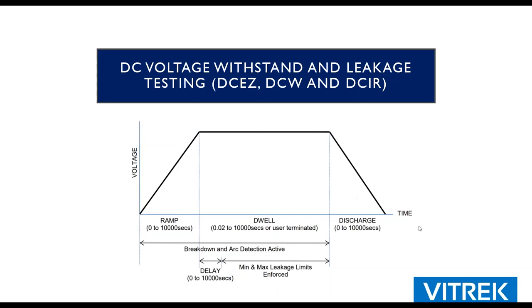We can apply different limits at different parts of the test. And importantly here, we can also have a delay. As you turn the corner from ramping to dwell, especially in DC, you could have very high charge currents right here. Then when we stop charging, you could actually have current reverse slightly or go to zero. And then what you really want is that current to stabilize and then take an accurate measurement. So we can ignore any noise that happens right in here and then get a really solid measurement result and hold your test requirement, make it applicable right here.